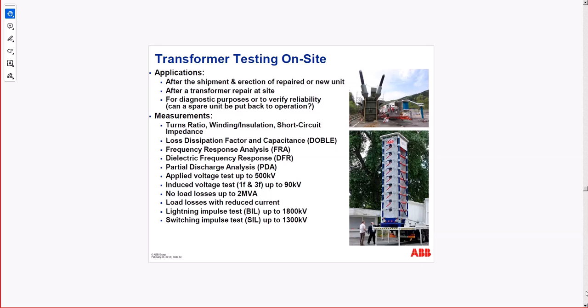So, transformer testing on site. Here are measurements: turn ratio as we did, winding insulation, short circuit impedance, dissipation factor with Doble or Megger. Those are the two main companies. Frequency response, dielectric frequency response, partial discharge, voltage test, 500 kilovolts. So measuring can happen at a voltage that is less than the rating. The high pot test only happens at a higher voltage, like 1.5 or 2 times the voltage, depending on the age of the transformer. And load losses, reduction, lightning impulse, and switching impulse. So those are the tests that you do on site.